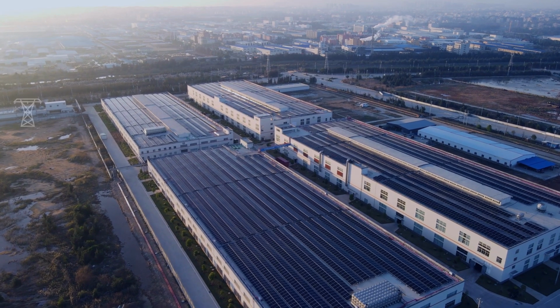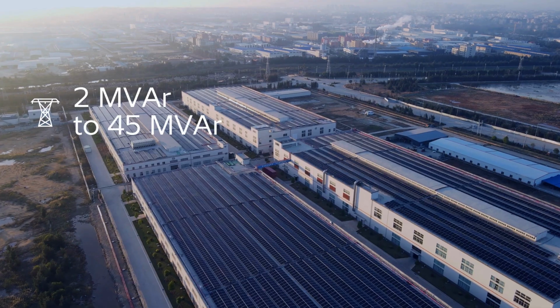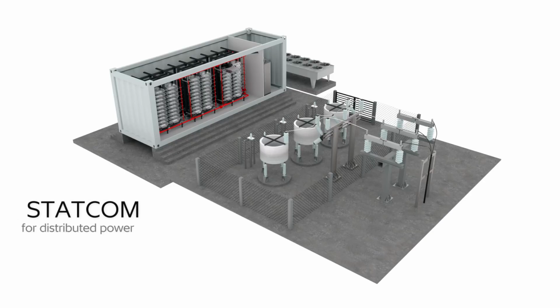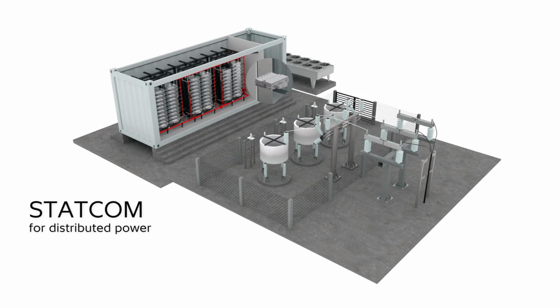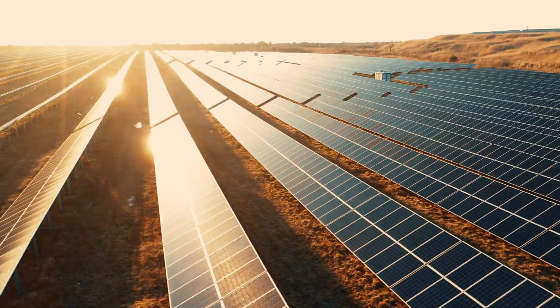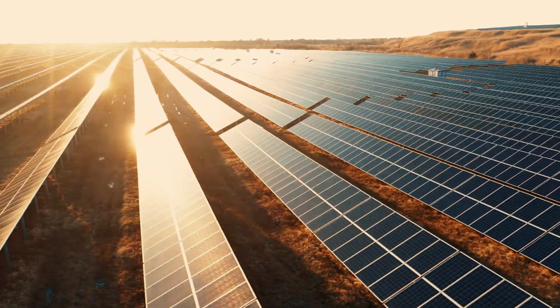It can support site requirements from 2 megavars to 45 megavars and features a modular and containerized design. Each STATCOM unit is pre-assembled and pre-tested, allowing for fast and easy installation, commissioning, and maintenance on site. Both indoor and outdoor STATCOM units are available to meet the unique requirements of the application.